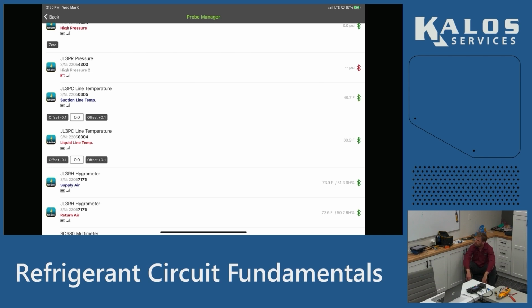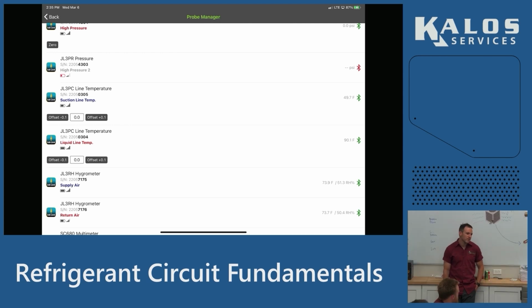Now the coil will freeze even if it has low charge, because it's below freezing. If it's still got enough charge in it to cool a little bit, it'll freeze the coil even though you've still got good airflow. On that one, and this is an experience thing also, if you come up to a system and the coil's frozen and you go outside and the compressor's frozen too, like there's ice all over your suction line, you've got an airflow problem, because you have enough refrigerant that you've been evaporating all the way outside. If you have a frozen coil and you go outside and you don't have ice all over your suction line too, you probably have a charge problem.